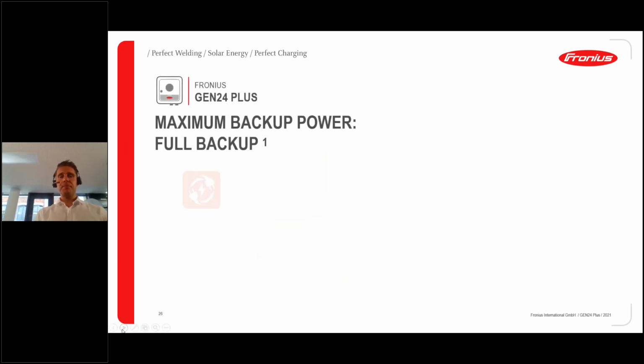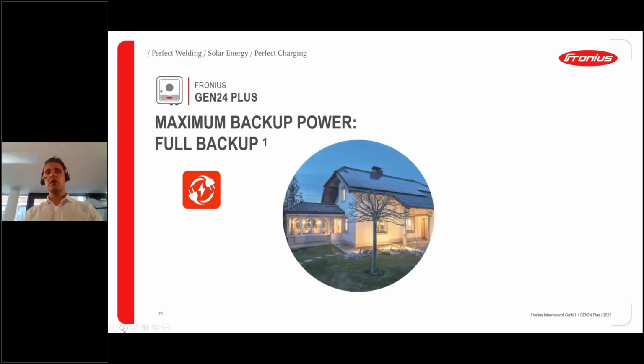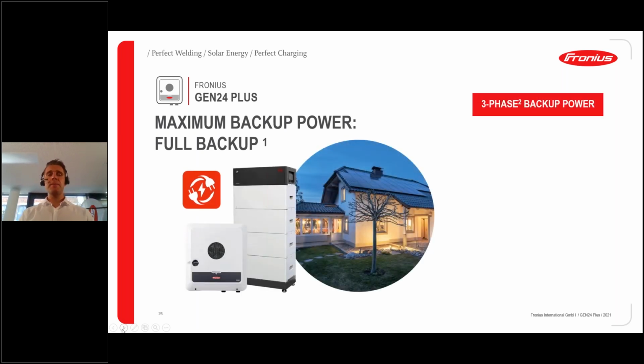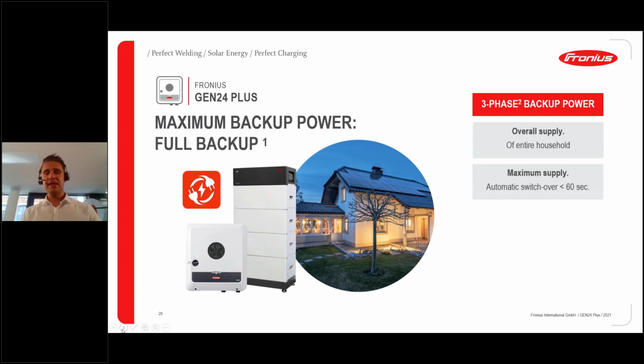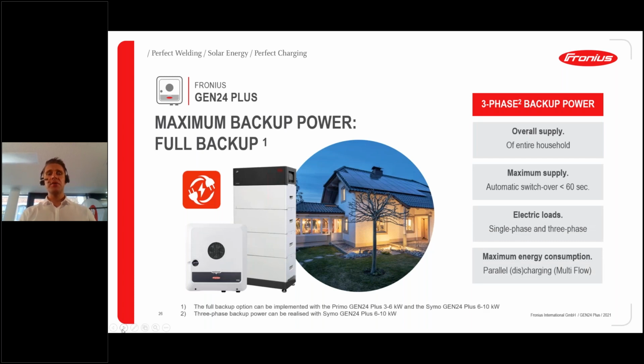Okay, that was the basic grid backup power function. What we also offer here is the maximum backup power. That's the so-called full backup. That's the second option you can take, which enables real three-phase backup power, and you have got an overall supply of the entire household if you decide for the full backup. What is important for the full backup?